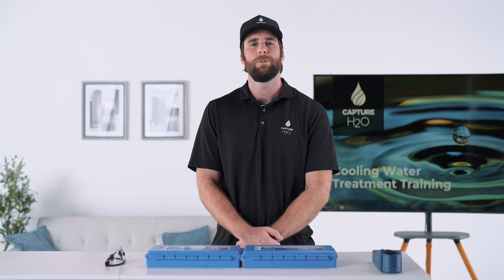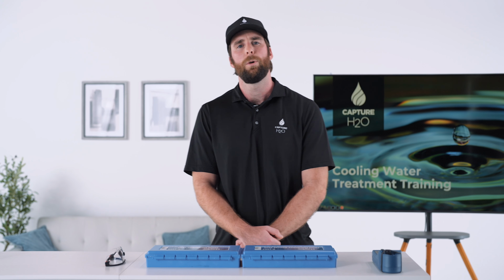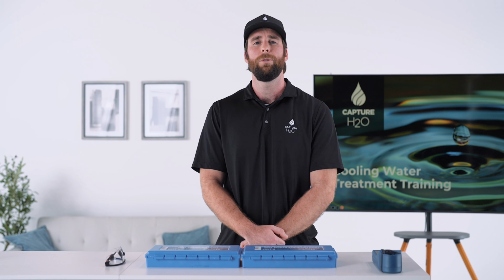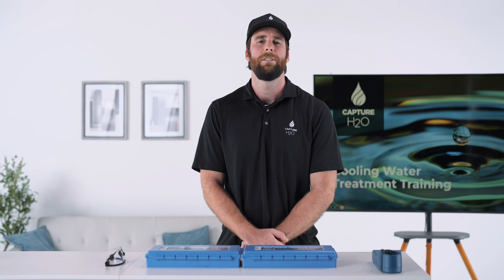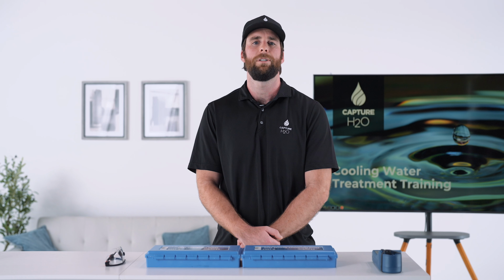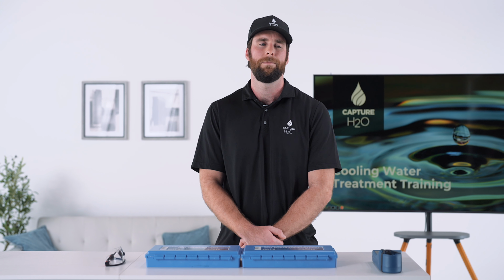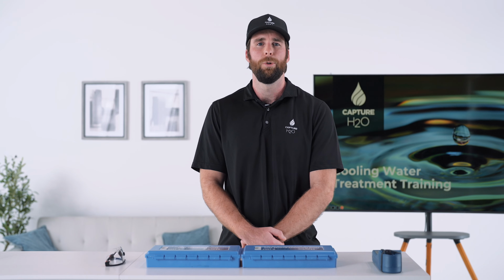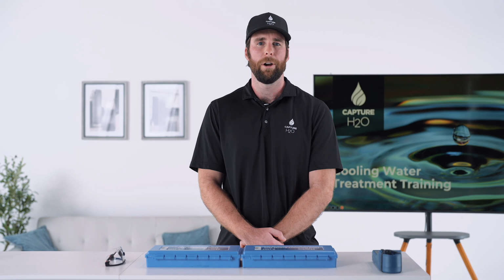When you detect hardness while doing your operator log, we will request that the first step be to manually regenerate the softeners. This is done by holding the recycle button on the timer for a few seconds. You will see it progress into the first cycle, which is brine draw slow rinse. It is critical to maintain salt in the brine tank at all times. This is the key component of softener regeneration. Without salt, you are going to see hardness breakthrough, requiring us to blow down the towers, again, wasting more water.